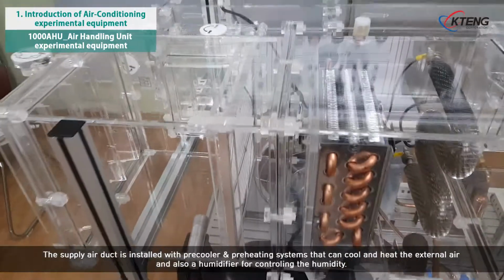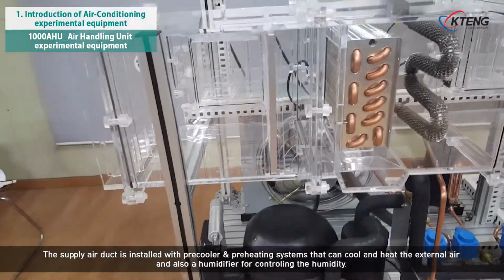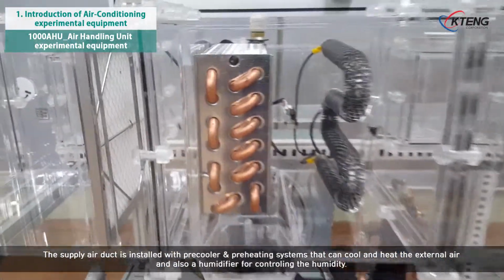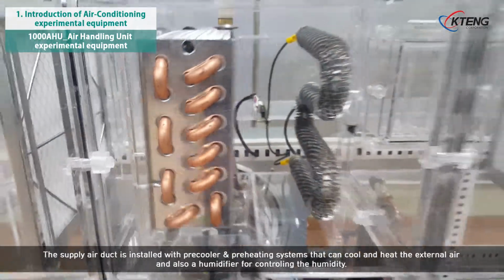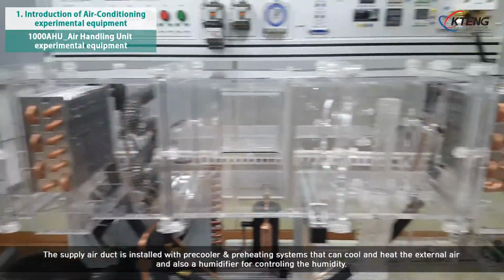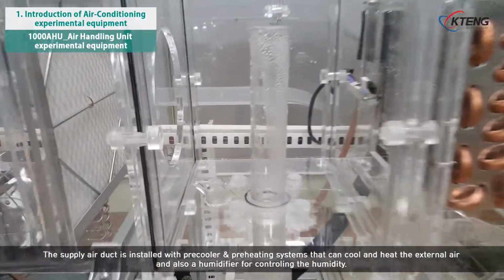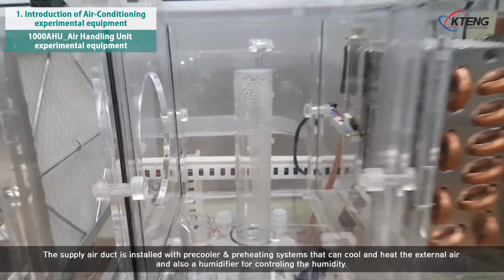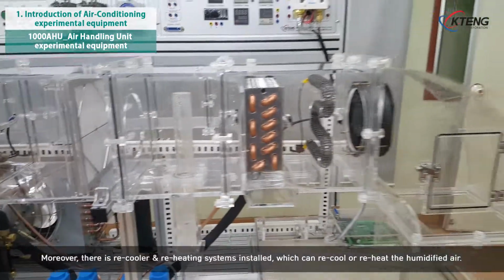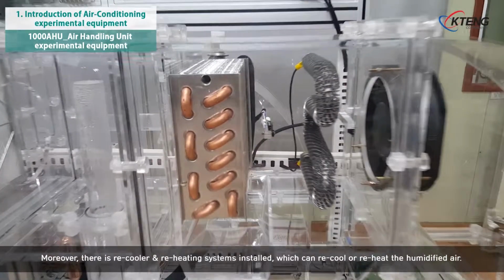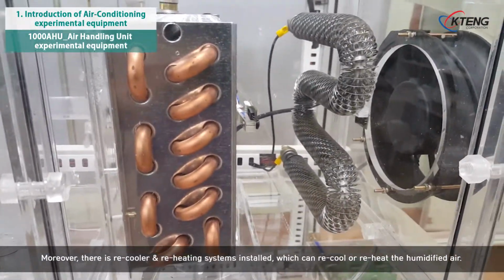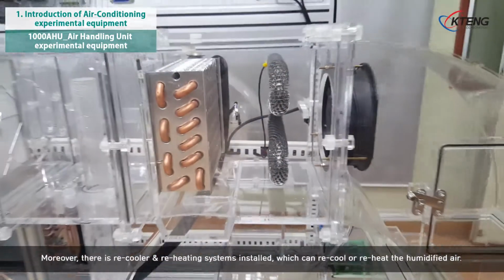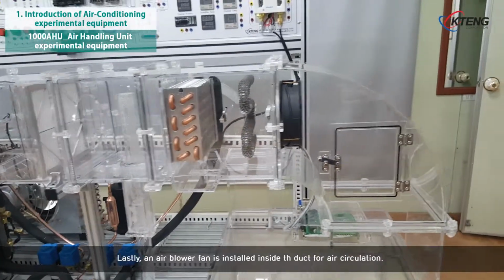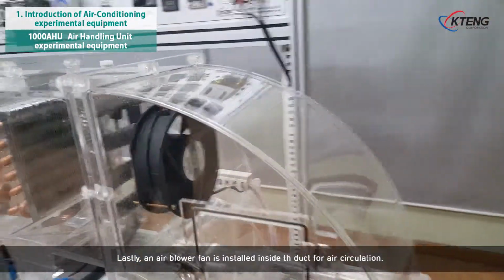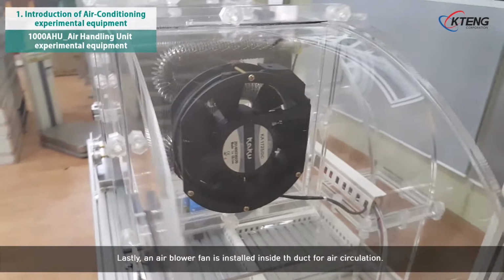The supply air duct is installed with precooler and preheating systems that can cool and heat the external air, and also a humidifier for controlling the humidity. Moreover, there is recooler and reheating systems installed, which can recool or reheat the humidified air. Lastly, an air blower fan is installed inside the duct for air circulation.